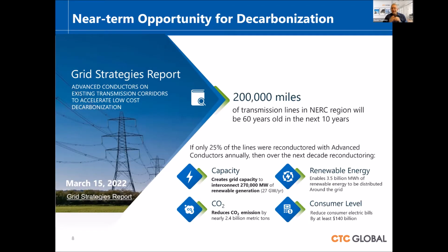Now I want to turn to a study that came out just 2 weeks ago from Grid Strategies, LLC. Their report was called Advanced Conductors on Existing Transmission Corridors to Accelerate Low-Cost Decarbonization. Very good report. There's a link. You'll get this after the presentation, and there's a hot link there for the Grid Strategies report. And I invite you to take a look at it. Short, but very powerful. In that report, though, they did an analysis looking at just old lines, not counting the over 800,000 megawatts that has applied for generation to get on and where that needs to be expanded, but just looking at old lines that are 50 years old and older.